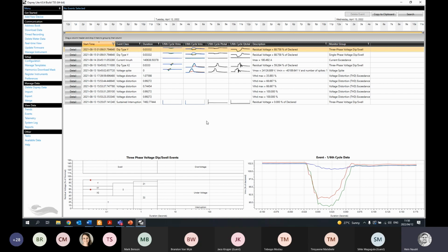Yeah, I understand what you're saying, but unfortunately, on Osprey Lite, you can't do that. On Osprey Lite, you can only individually analyze meter points. So you always need to specify a specific meter point, and then you can view the trends for that specific one. Whereas, as you mentioned, on Osprey Pro, you will be able to view your whole fleet of units on one page with all of the events, and it will also group events that were recorded at the same time into one incident because they were caused by the same thing. So that you can't do in Osprey Lite, unfortunately.